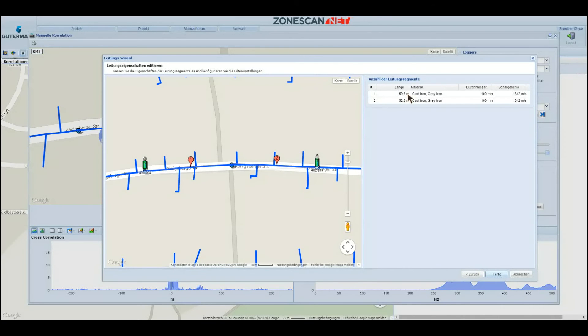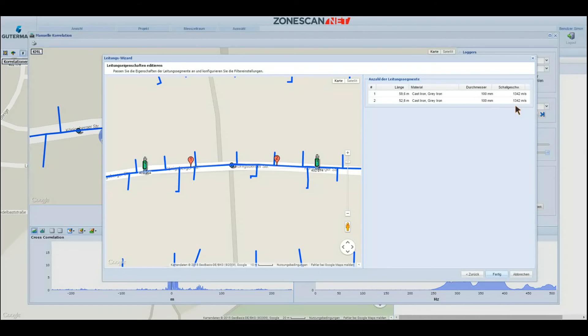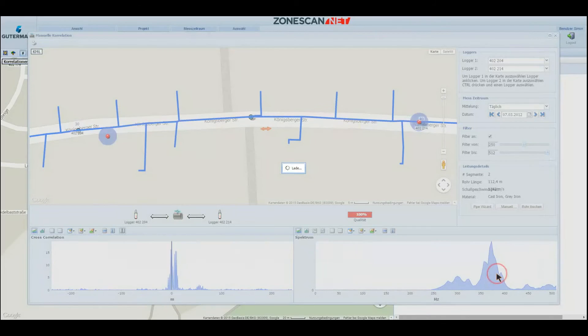Proceeding to the last step, in which you can define the materials and diameters. In this case, nothing needs to be changed. We have grey cast iron pipes with a diameter of 100mm, resulting in a sound velocity of 1342m per second. When you click done, the system recalculates the correlation based on the inputs you made.